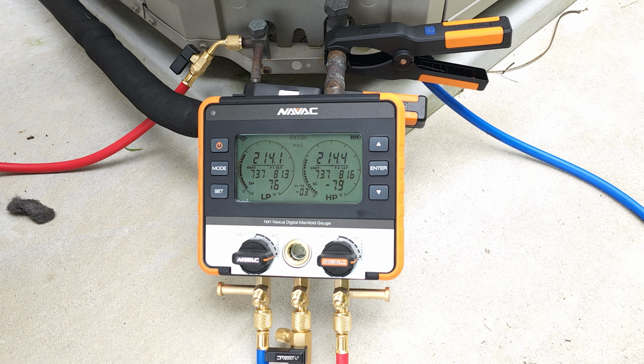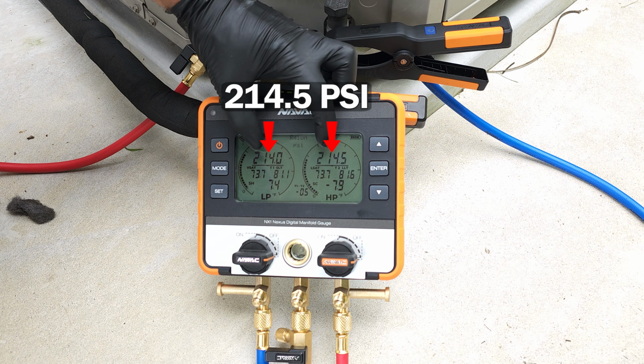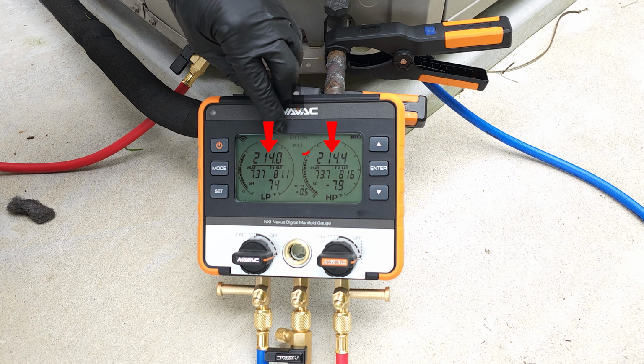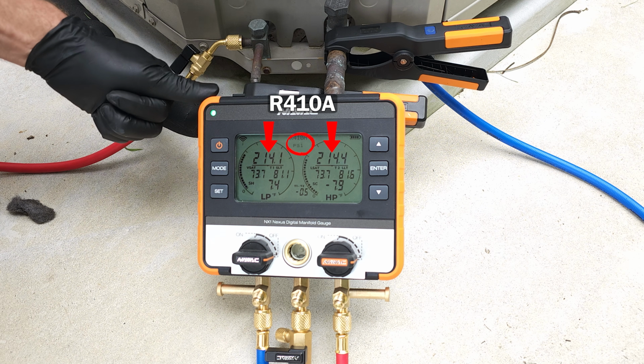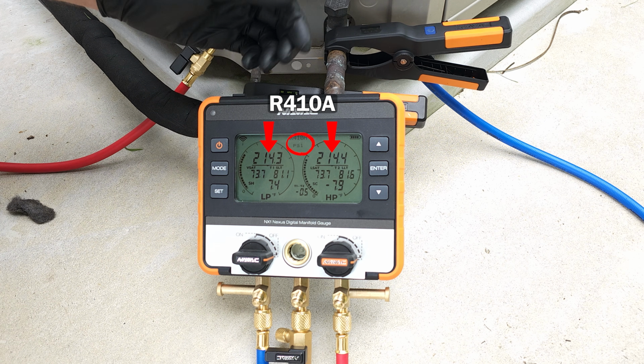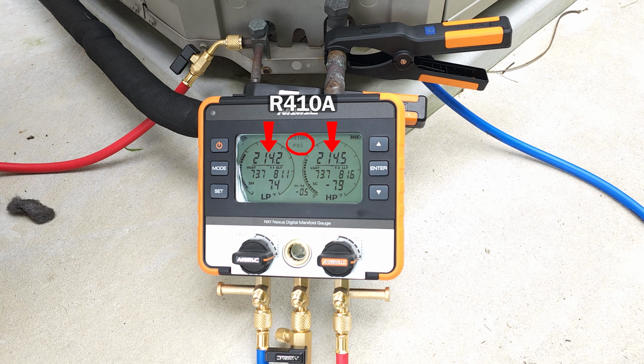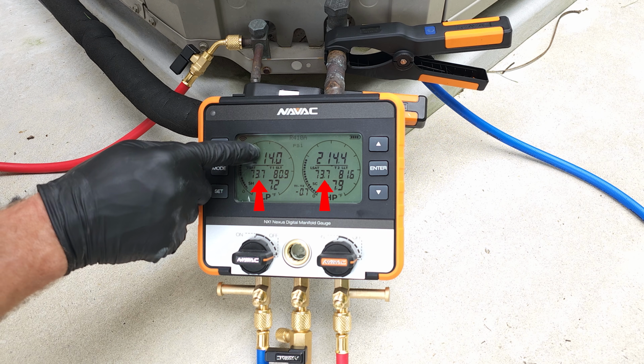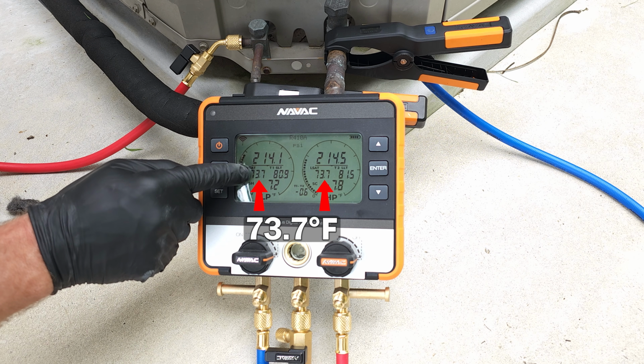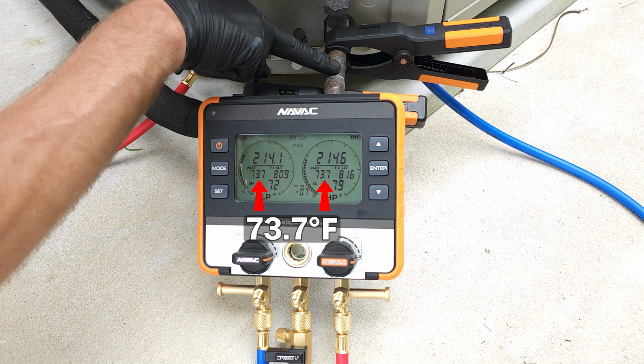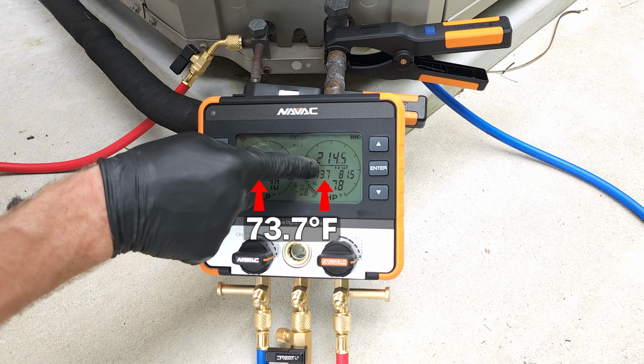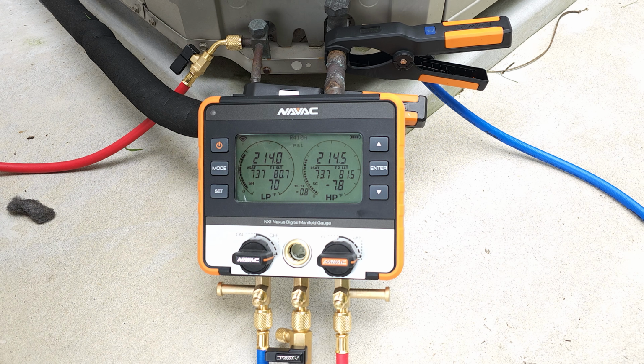Now we can go ahead and turn the system on, and we're going to monitor both the pressure, which is right here, 214.5 psi. We have R410A selected because this is an R410A system. This system has a thermostatic expansion valve on the indoor unit. And right over here, you're going to see the pressure converted to saturated temperature. So the saturated temperature of the refrigerant in the tubes right now is 73.7 degrees. You can see it on both sides. And so let's go ahead and turn this system on and see what happens over on the suction side.